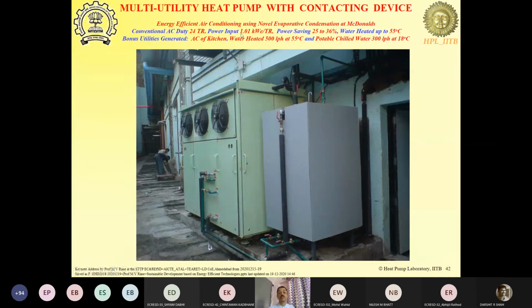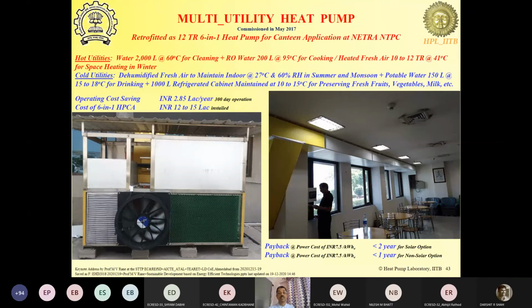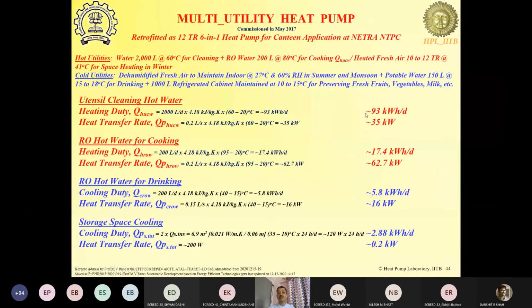Okay, more than this. So I have already described to you this unit. Here the power input was only 1.01 kilowatt electric per ton. And compared with comparable systems at that time, the power consumption of our system was 25 to 36% less than the air-cooled unit which we replaced there. Then this I have described to you in detail. These are the calculations. So although this is only a 12-ton heat pump, the instantaneous heating duty can be as high as 35 kilowatt of water heating, and 62 kilowatt of potable hot water for cooking. So at 90 to 95 degrees centigrade, if you get hot water, you just put rice in it and it will cook itself without heating. For vegetable and dal, of course, you need to continue to heat it and process it.